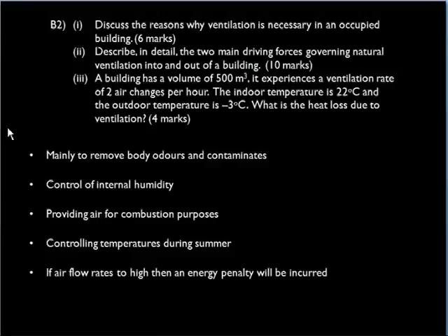Also, we need ventilation to control internal humidity. If the internal humidity is too high, there's a risk of condensation, especially in the winter months. So we will use ventilation, either natural ventilation or mechanical ventilation, extraction fans, cooker hoods, etc., to remove water vapour where it's been generated.